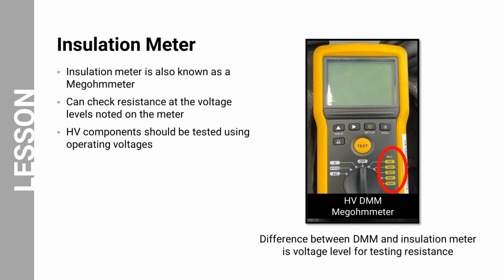Insulation meters, also known as megohmmeters, play a vital role in isolation fault testing as they measure electrical resistance, particularly at high voltages compared to a standard digital multimeter, DMM. The high voltage capability allows an insulation meter to evaluate the integrity of insulation in high voltage systems, where even small leakage currents can be dangerous. The meter can be set to various voltage levels depending on the specific component or system being tested.